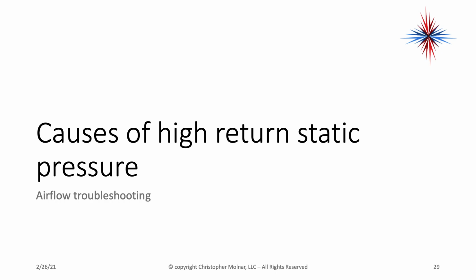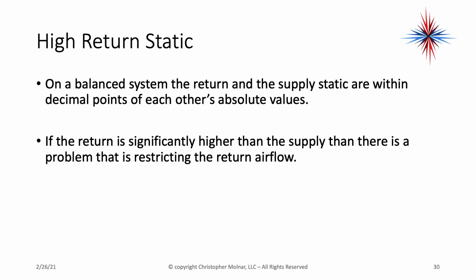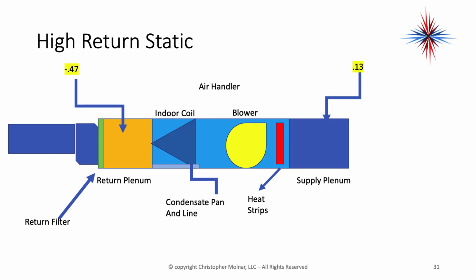So let's talk a little bit about the causes of high return static pressure, because the return side of the system is where we have to start. On a balanced system, the return and the supply statics are within decimal points of each other's absolute values. If the return is significantly higher than the supply, there's a problem that is restricting the return airflow. So if I have like a 0.47 and a 0.13, I got to find the problem because my return static is too high.